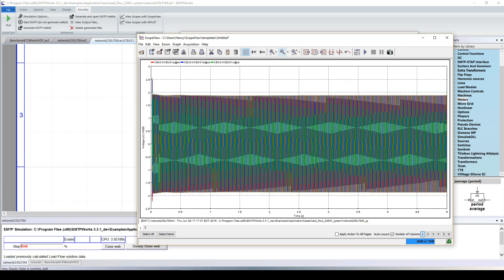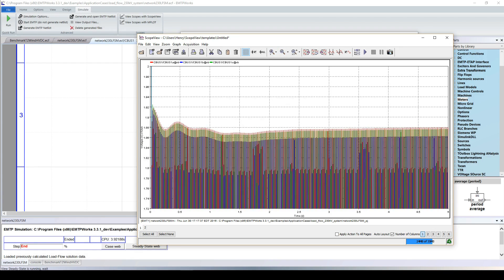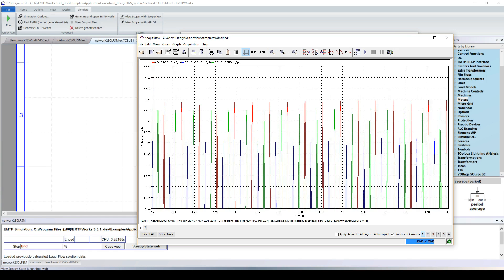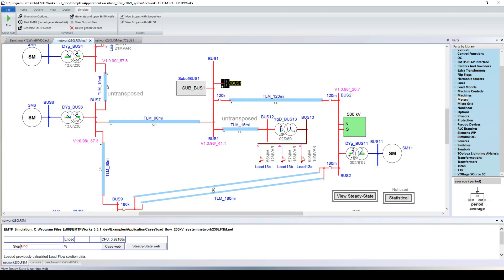Zooming in on the voltage crest, we see a slower variation due to the voltage regulator and governor of the synchronous machine adapting to the new steady state. Zooming further, we can see that the voltage on each phase is not the same, because this network is unbalanced — there are different loads on each phase and some untransposed lines.